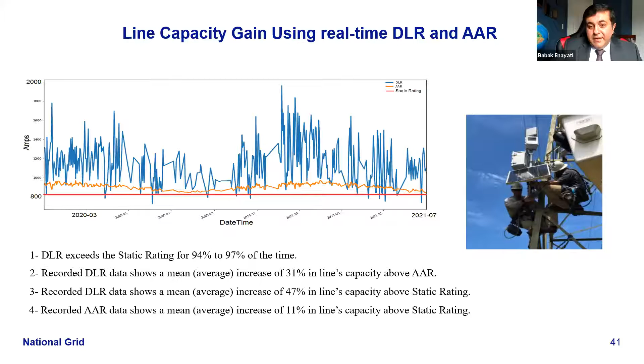Recorded DLR shows a 31% increase in line capacity over ambient adjusted rating, and a 47% increase compared to static rating. Comparing ambient adjusted rating with static, we see an 11% increase. So look at the difference between the DLR increase versus the AAR increase, both compared to static.